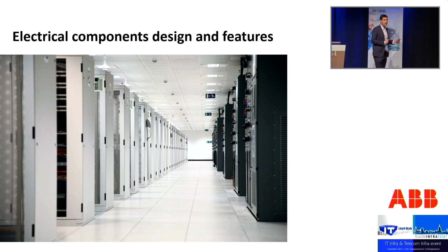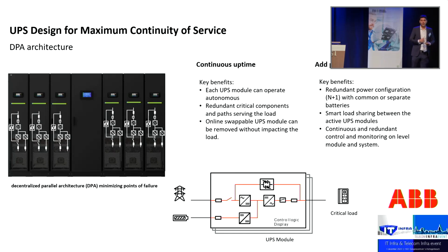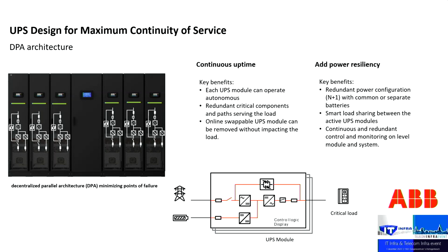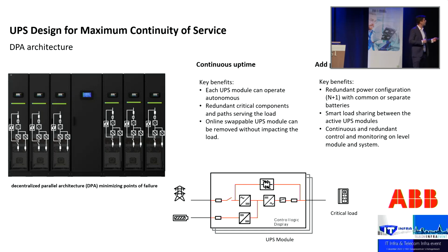And now I want to deep dive more on the component base. So one option is to improve this system. The other, not option actually, one opportunity is to improve the system. The other opportunity is to properly choose and design also components. In the heart of the data center, I would say lies the UPS. As we said, UPS is there to protect my loads if I have any abnormal condition or a failure or anything else. So I also should build a redundant UPS, so I can also have N+1 architecture inside of the UPS, but I want to have a real one.